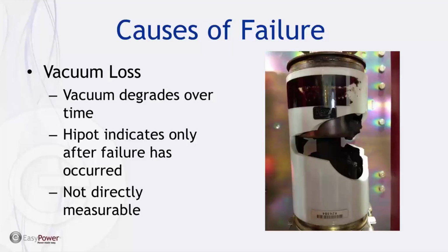Different surface finishes can actually affect that outgassing rate, such as electropolishing or other types of treatment like that. Another type of virtual leak would be a trapped volume of gas. This could be something between a braze joint, if two parts weren't properly seated and the joint was able to seal but trapping gas at the same time. Those pockets of gas can be released after a period of interruption or melting inside of the VI, and that could cause a drastic increase in pressure.